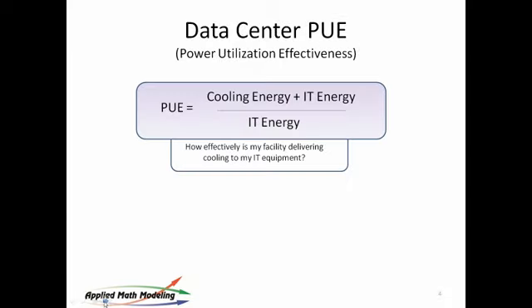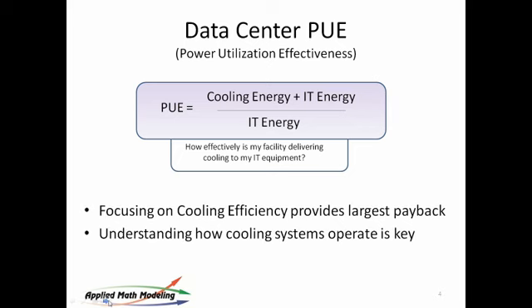So PUE is really, from a dominant parameter point of view, cooling energy plus IT energy divided by IT energy. If you look at the metrics and which ones are dominant, it's really cooling energy. And focusing on cooling energy, therefore, and cooling efficiency provides the biggest payback, the biggest return on investment. And understanding how that system works is key from both an operational point of view and, of course, a data center design point of view.